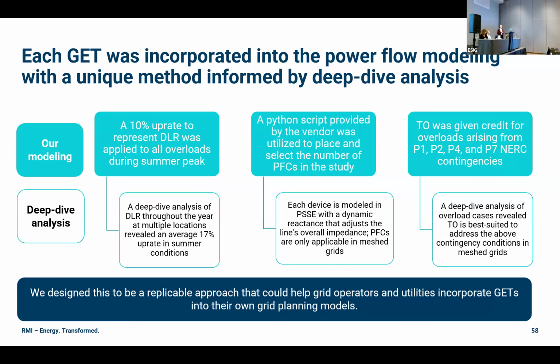So how did we do this? Like I said, it's very new to apply grid enhancing technologies to the planning paradigm. So our approach was to do a deep dive analysis separately for every single grid enhancing technology and have that inform how we were to apply them to our power flow modeling. For example, for DLR, we chose multiple locations on the PJM grid and had a vendor conduct a deep dive analysis at all of those locations to reveal what the uprate would be at every hour of a representative day of every month out of the year.